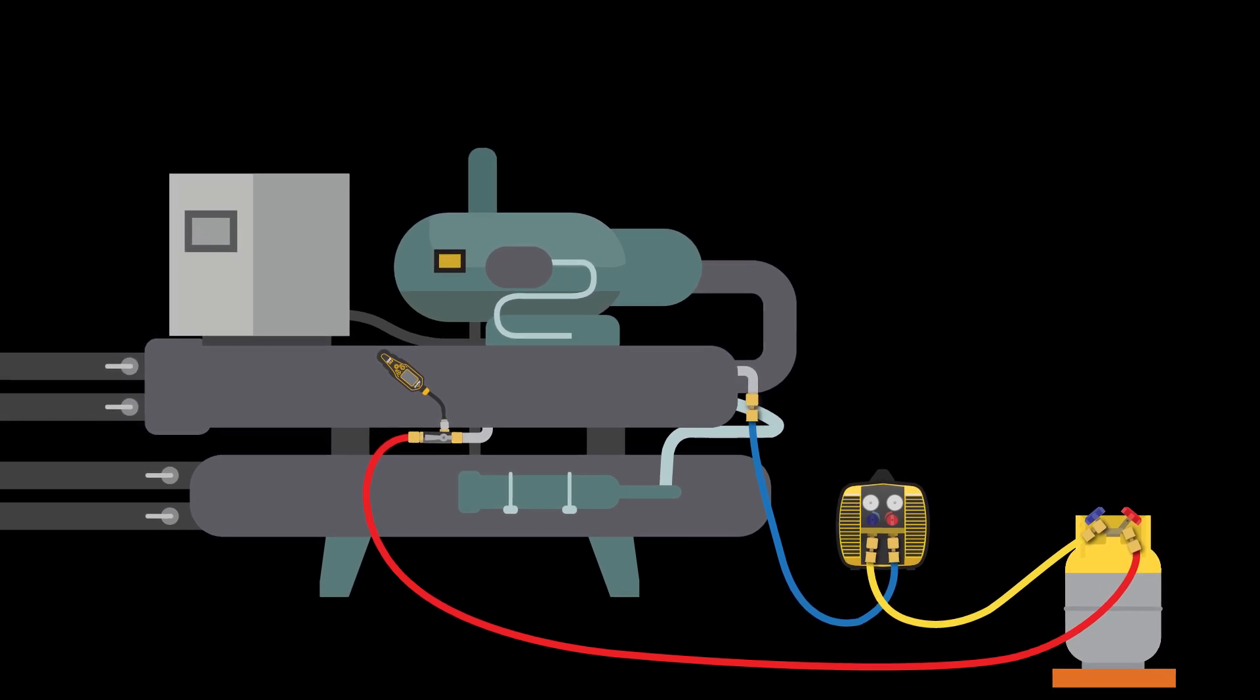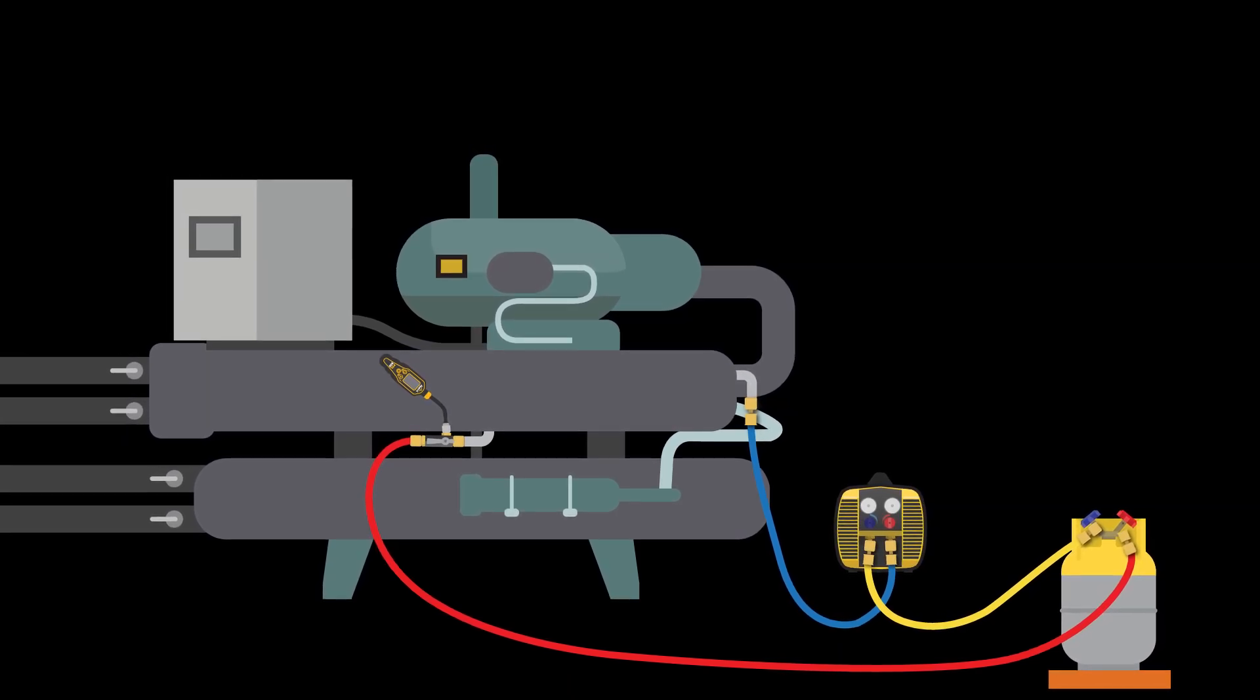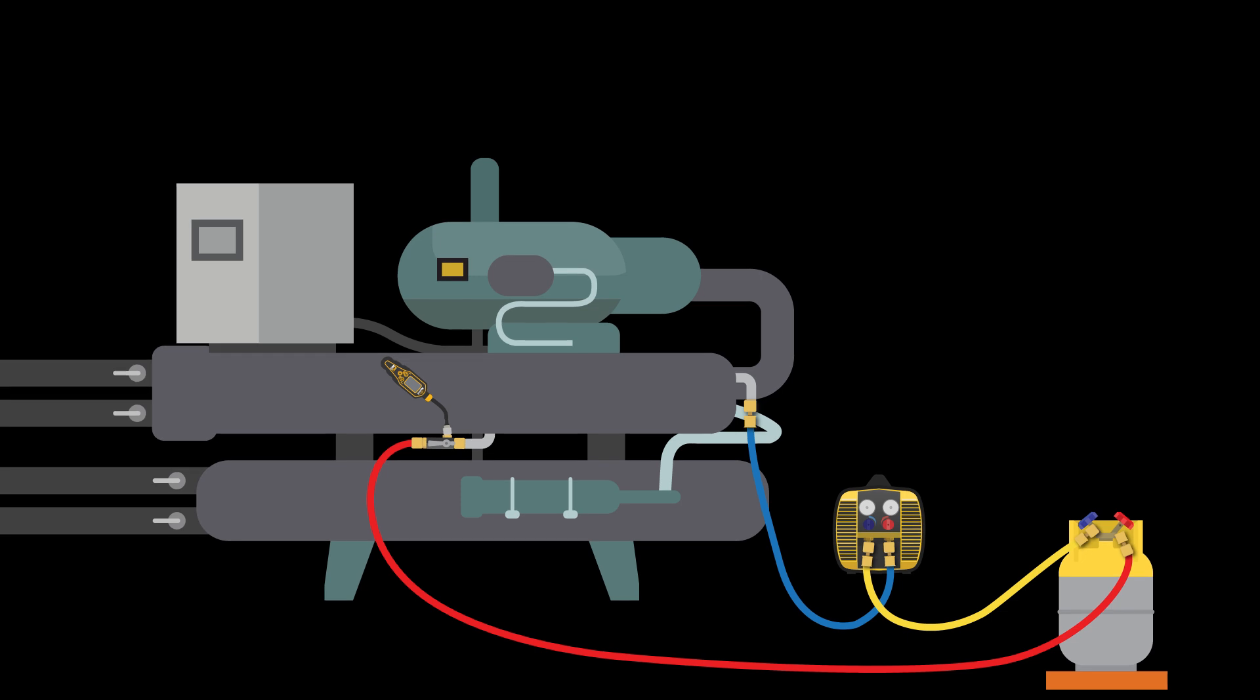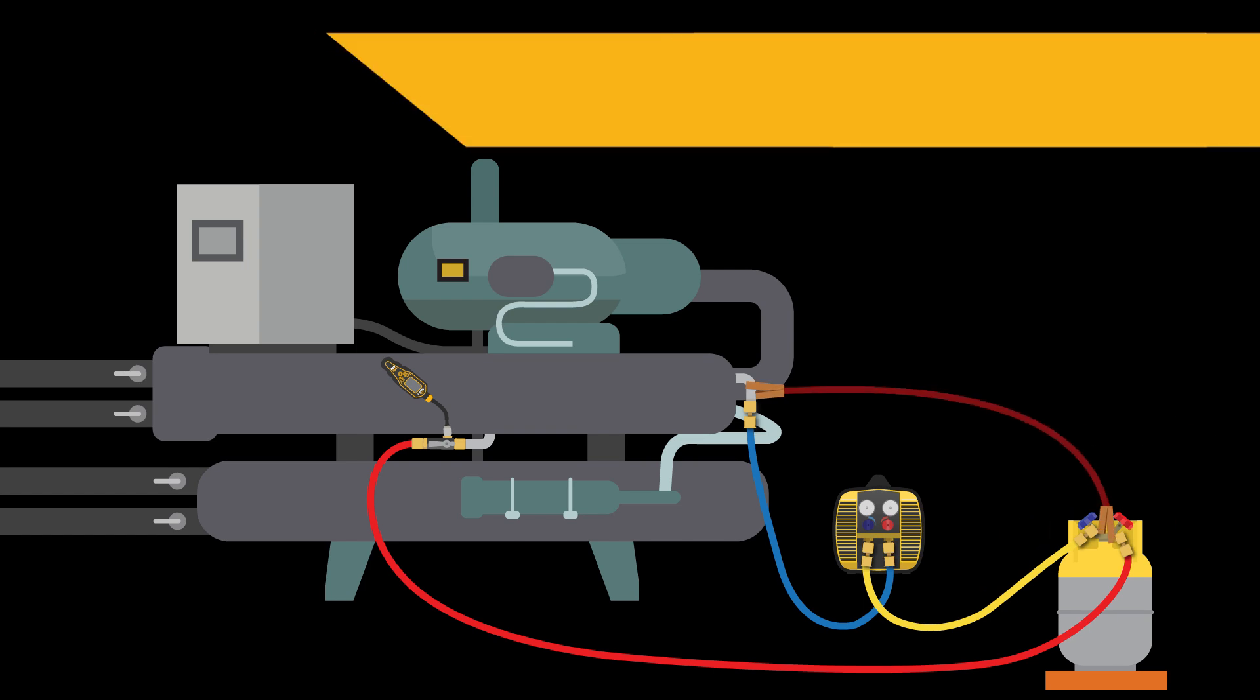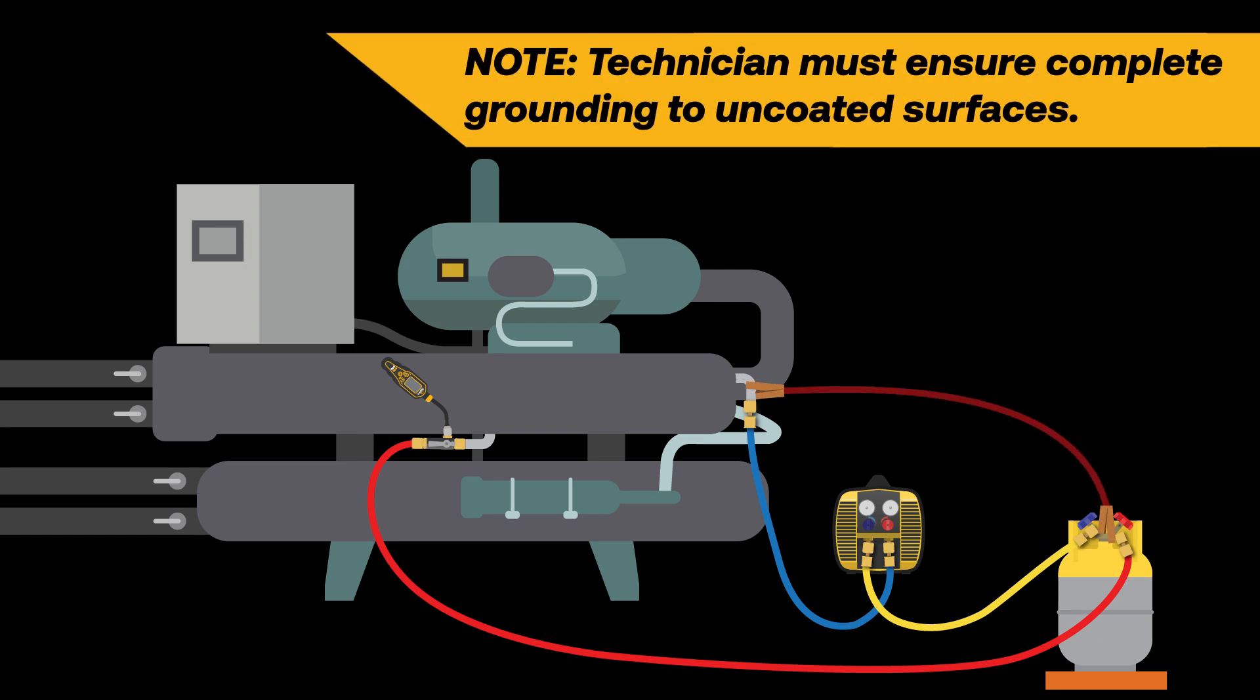When moving refrigerant at such a high speed, a transfer of electrons between the refrigerant and hose lining can occur. This often leads to a static charge building in the recovery cylinder. Attaching a grounding cable between the cylinder and a known good ground will allow this charge to dissipate before building to a state that could jeopardize your safety and the safety of those around you.